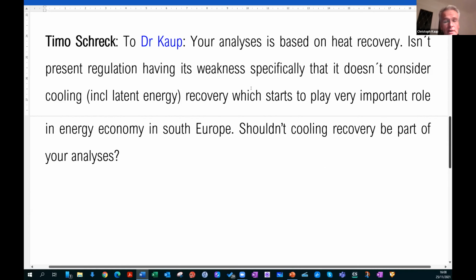Yeah, that's a good question for sure. But as you already said, that was a really complex job which I did. And if you look at the EU regulation, and maybe Davide will state that also, even the old EU regulation of 2014 didn't take into account any kind of humidity changes, dehumidification or humidification. And that was the reason why we just concentrated on sensible cooling loads. And for sure, it would be very interesting to do this analysis also for dehumidification and humidification issues.